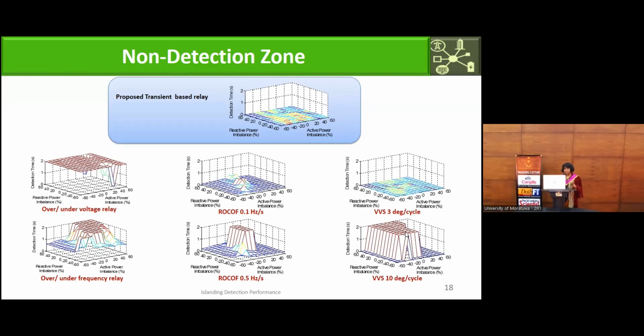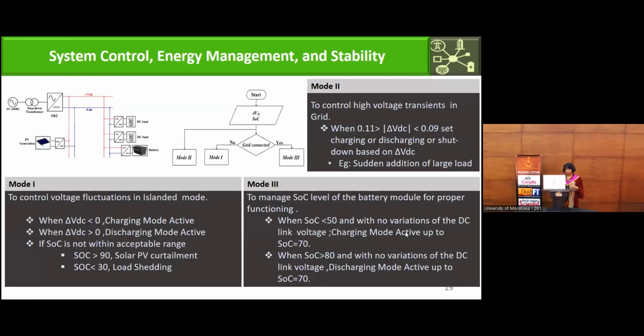Such systems are very good for application in microgrids, and we don't need any communication because the measurements are done at the generator itself, so that is avoided. Now in our monitored microgrid, we are having voltage and frequency measurements. After that, the breaker signal is given as a communication signal to the main controller, because central control is used. So depending on different criteria, we can select the islanding detection technique, but fast detection is always important. This is one of the things where we can do more research.